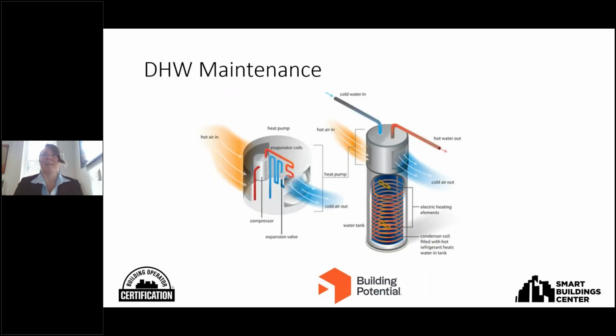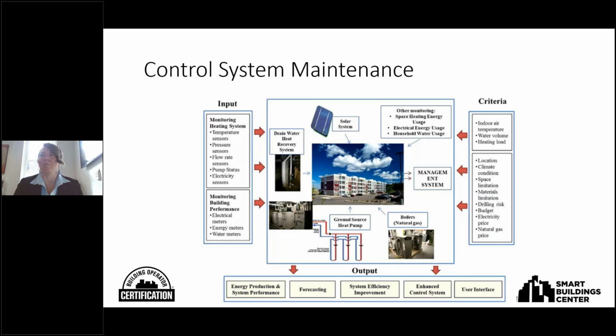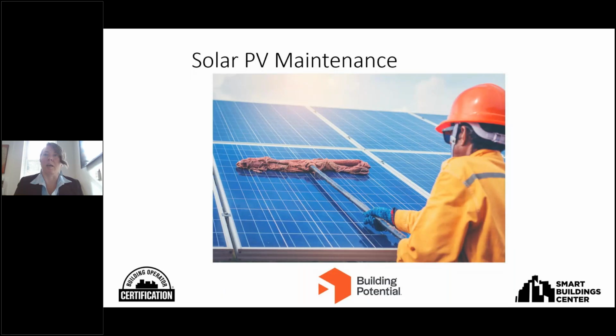Domestic hot water maintenance, control systems—making sure your controls are optimized. How many times have we changed or overridden our HVAC controls for, say, an evening event, and that never gets changed back, and we never know because we're rarely in the building in the evening? Holiday schedules, a tenant moves out and the use or occupancy schedule is different. So maintaining your controls is important, especially when adding new equipment, to make sure you're applying that accurately.